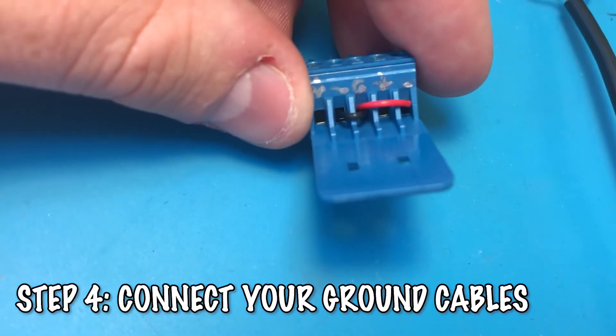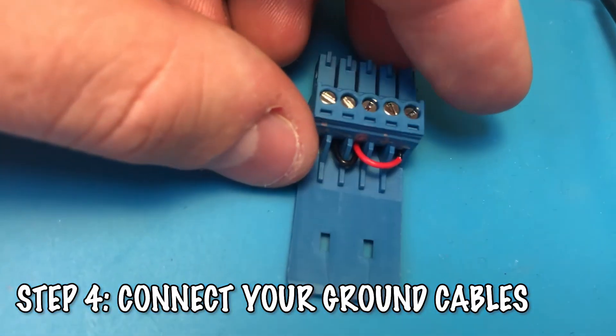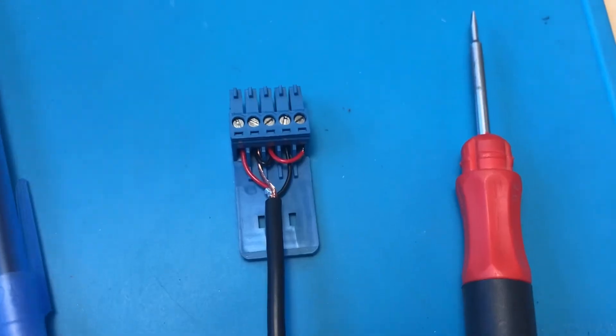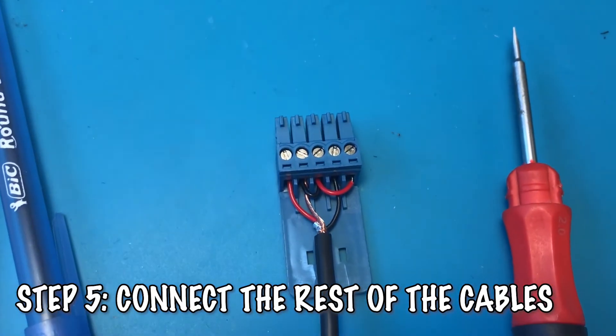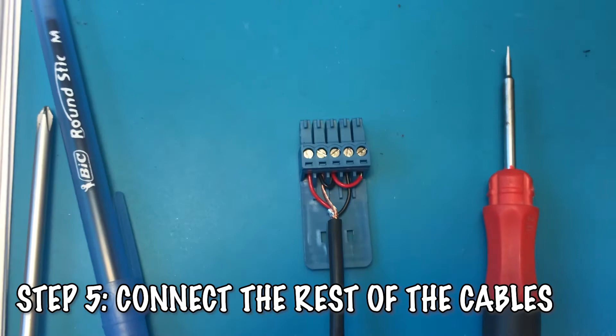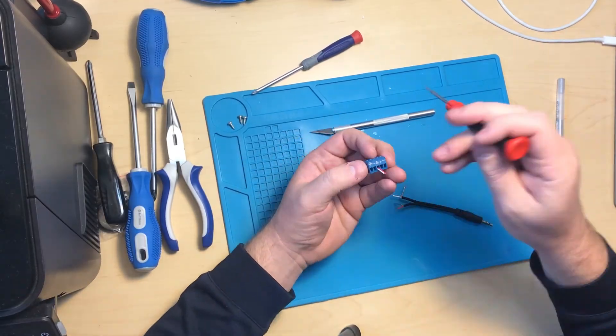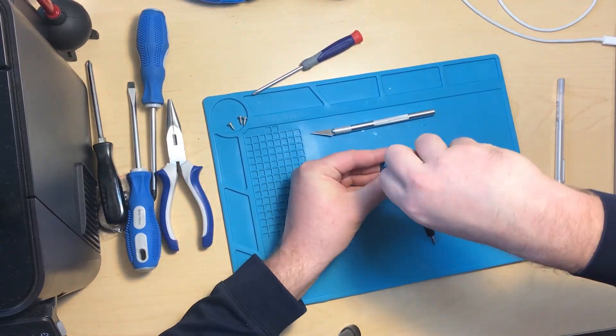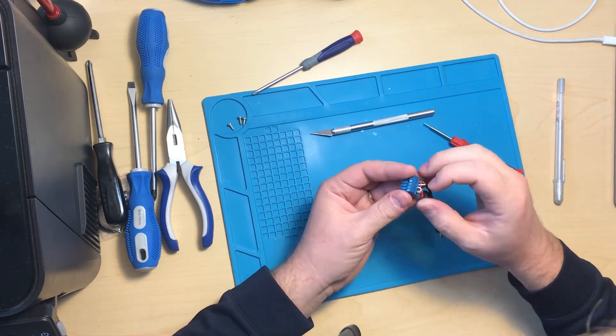Connect the jumpers into the negative terminals and bridge them to ground. Connect your ground wire, and then connect the other wires according to your diagram. Once the wires are tightened into place, check for any loose connections, and then install the Phoenix connector into your device.